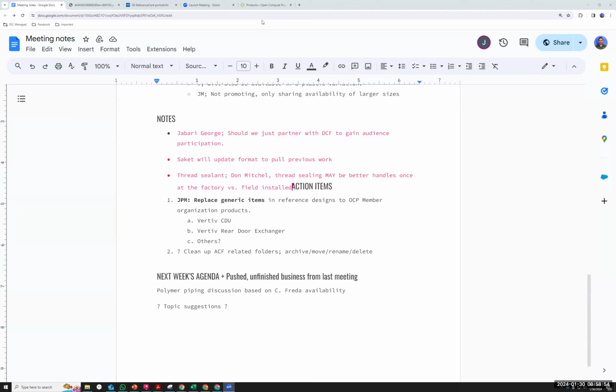I'll add to that. The door heat exchangers today are largely fin and tube constructions, right, Don? Copper and aluminum. If you go to compact heat exchanger technology, now granted the channels are still going to be larger than they are with the chip coolers. And the chip coolers, by the way, we've heard numbers that say up to 25 microns between the inside faces of the cooling fins, which means you've got to have 10 micron or smaller particles to avoid accretion between them. But on the compact heat exchangers that can potentially be used in other areas, it's a bigger number, but still it's a bigger concern than it is with the fin tube style.